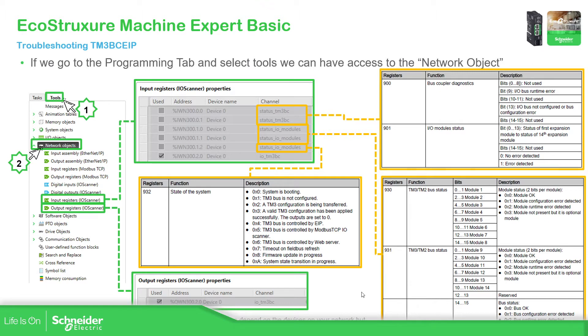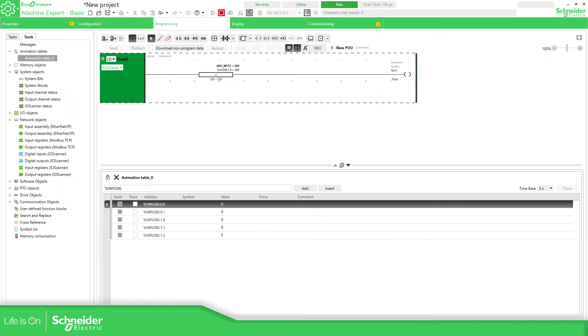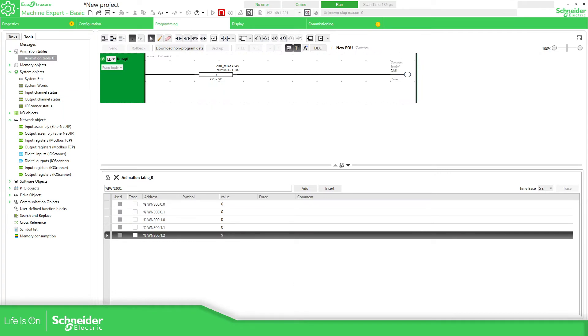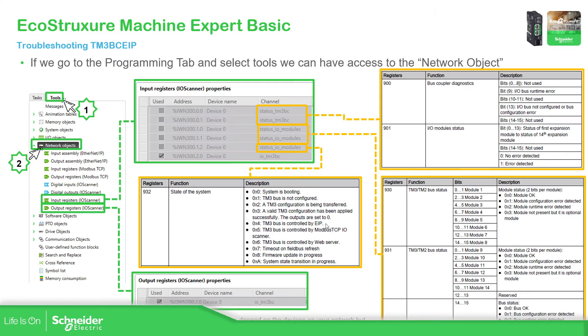If we check right now what's going on, this one is value five. So number five means that the TM3 bus is controlled by the Modbus TCP IO scanner. So this is valid.